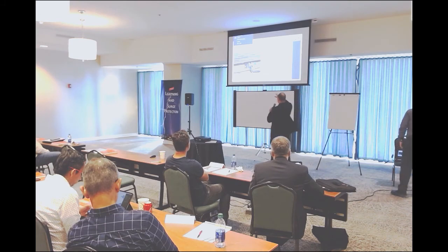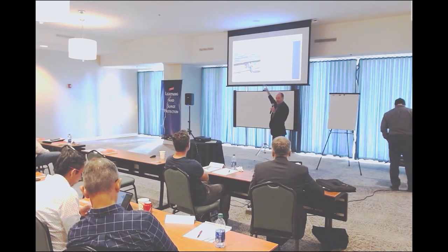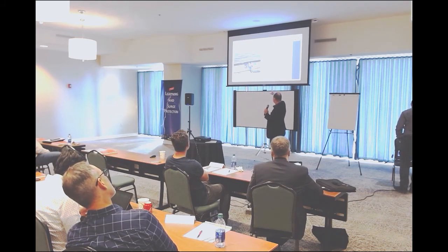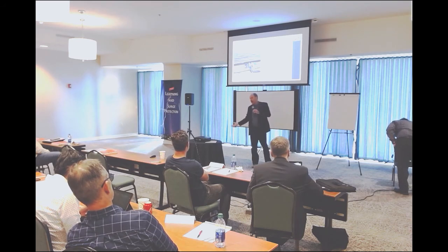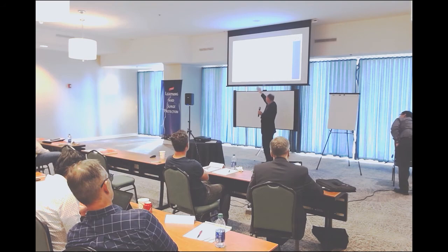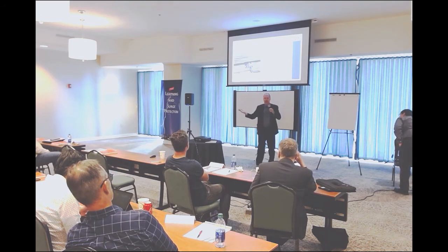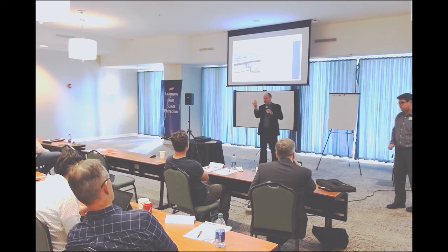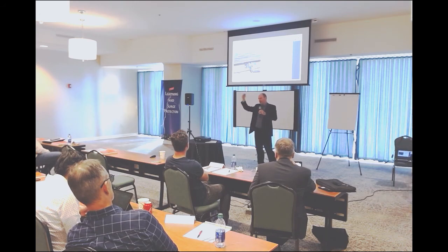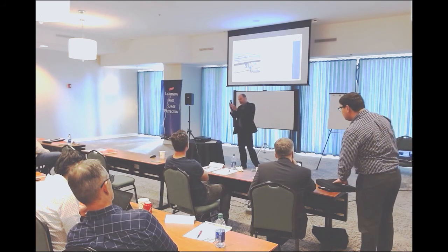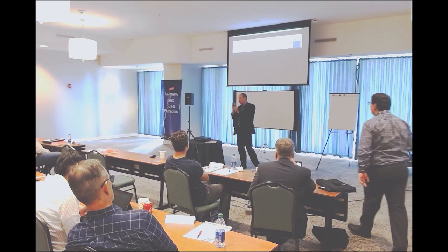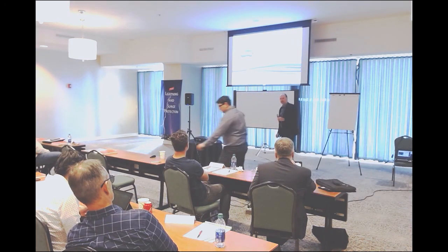So then you can do a more complicated structure and you can show the outline of where you would need your down conductors and your cross, sort of the building mesh that's across the surface. And from that, you can calculate all your separation figures and show if the HVI product is sufficient for that location, because out pops the number 7 in centimeters. And we can go to our product tables and show that product has up to 90 centimeters of separation equivalent space, but you're going to install it at zero separation to the actual target victim.